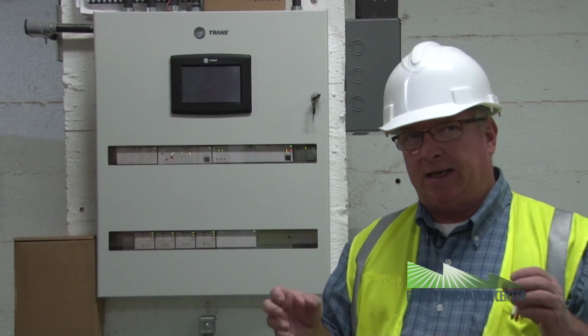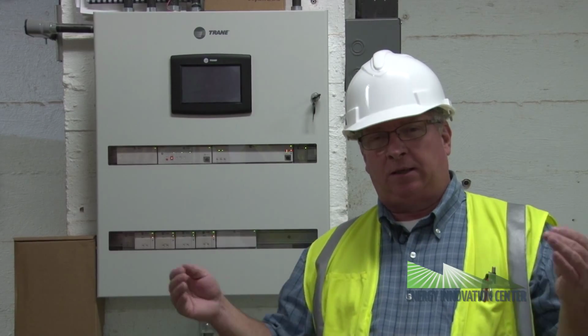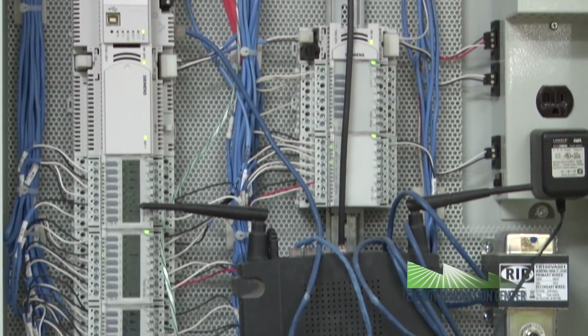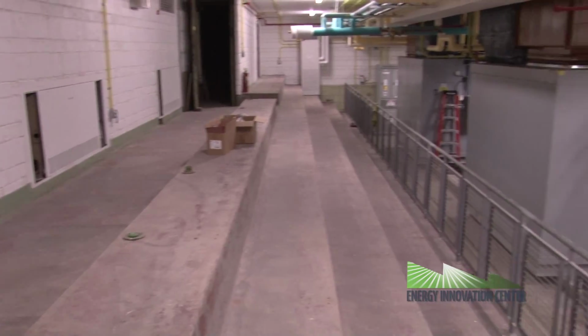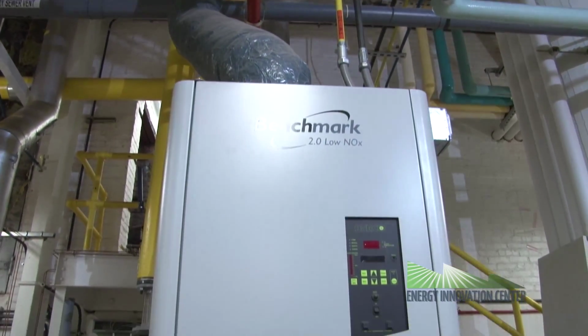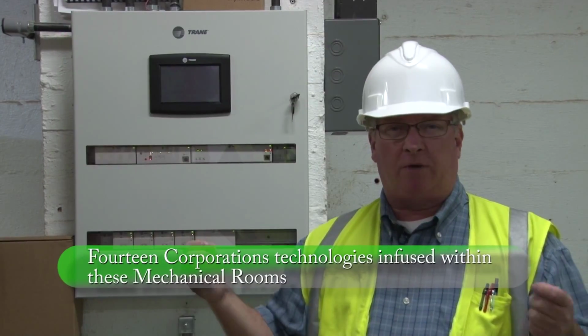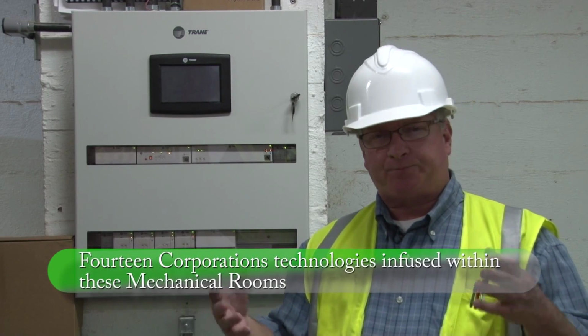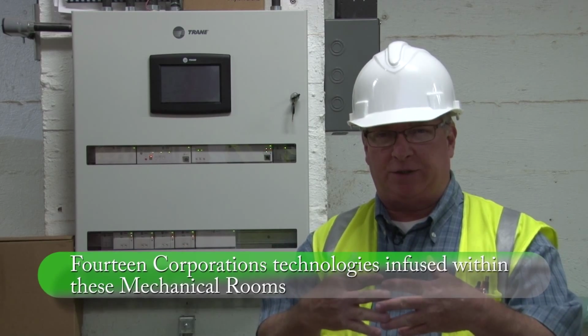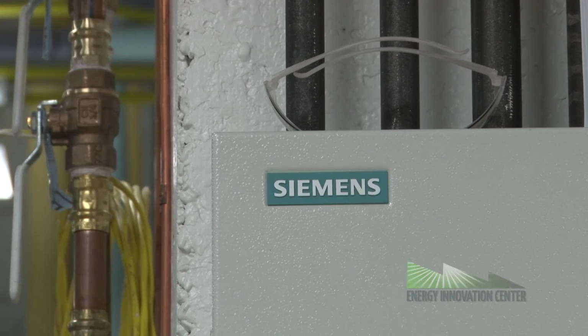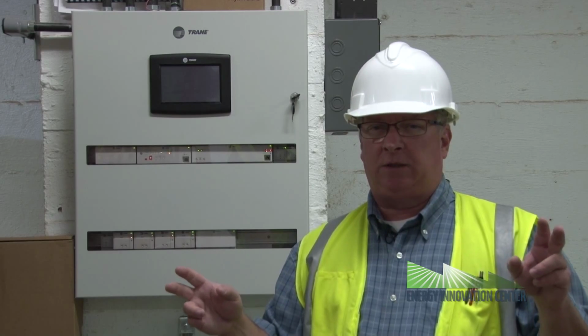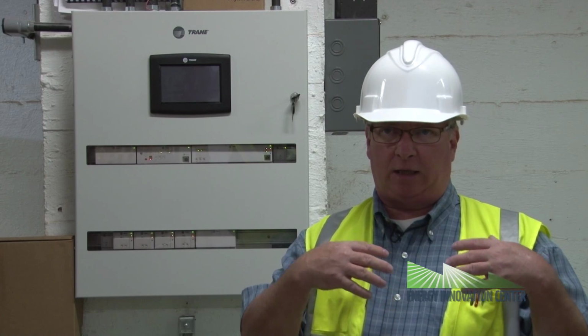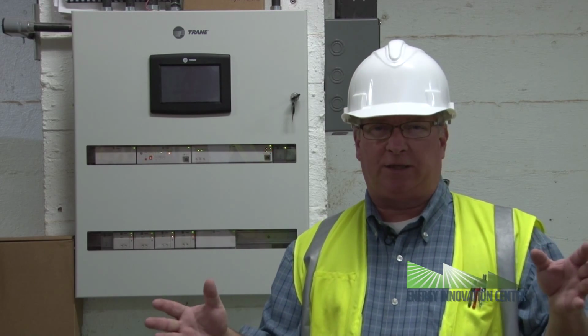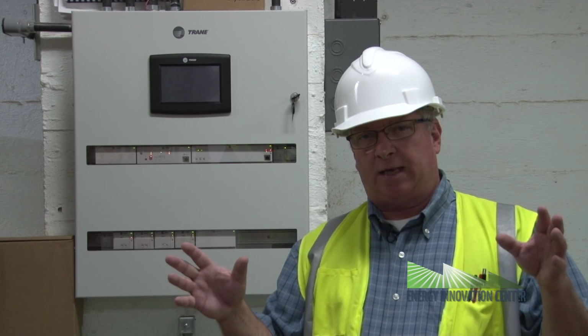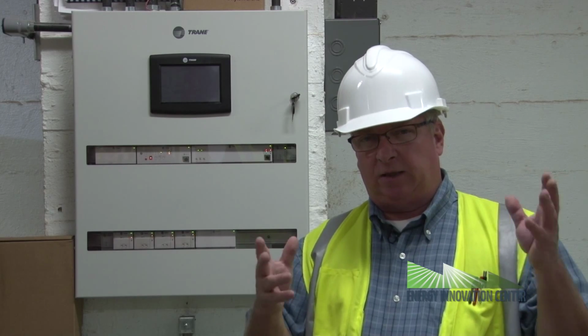This is the Trane control panel for just the ice making system. This facility has 7 different building automation systems in it, and we integrated them all into one front end. So the 7 building automation systems that we have: the dedicated outside air system has one, the boiler system has a second, the chiller has one, and we have other multiple building automation systems in the building. We've taken all that data via BACnet communications, and we're feeding it all into the Siemens base building automation system. So it's a true integration of multiple systems that a lot of buildings are not actually doing. This building is actually utilizing all of this data to come back into one front end.